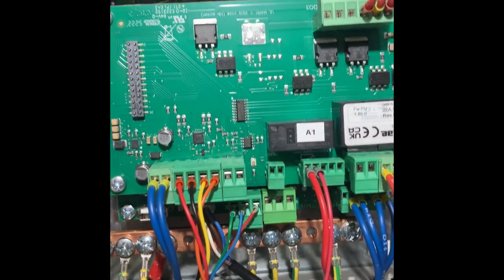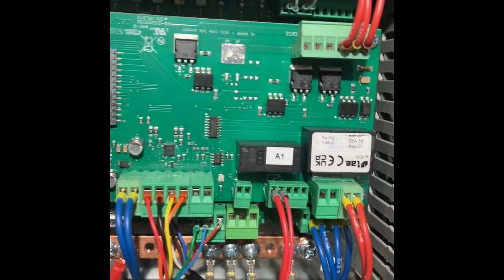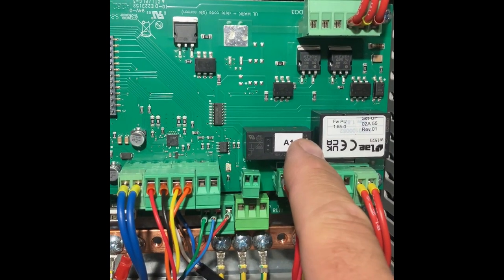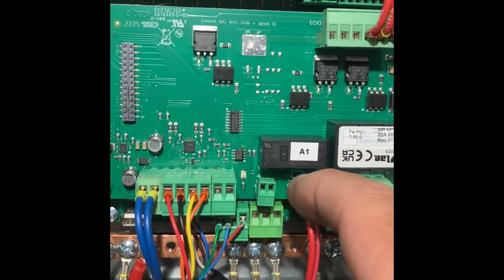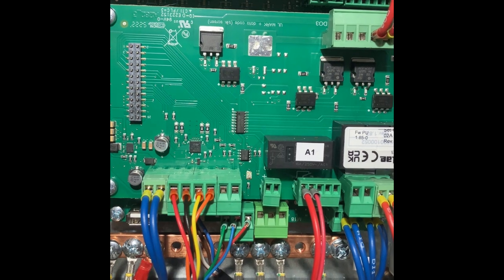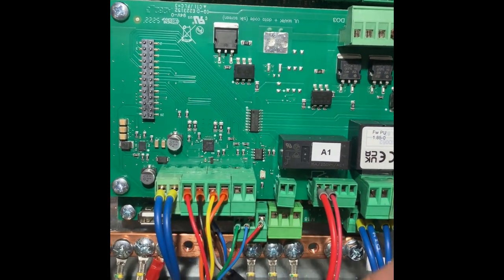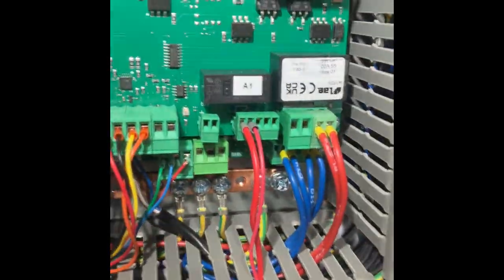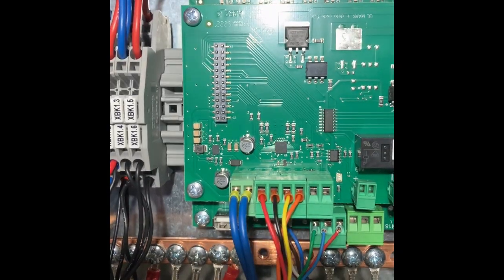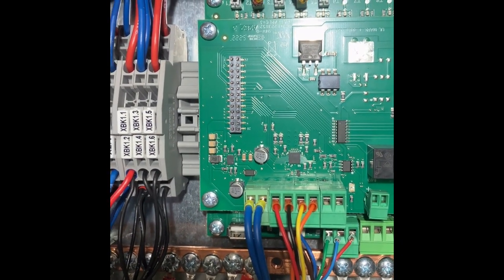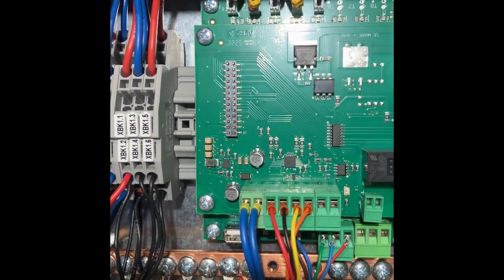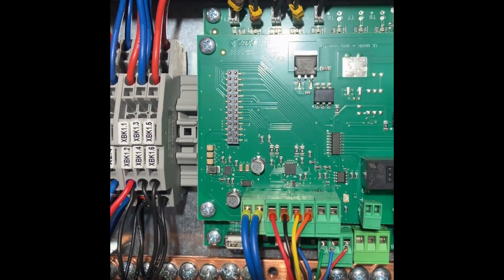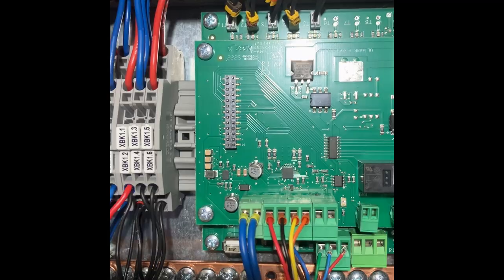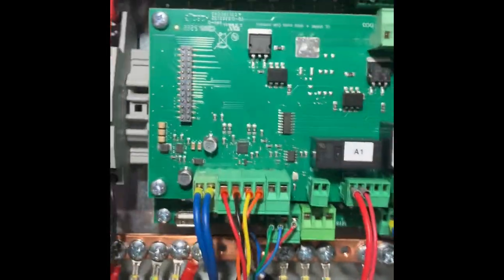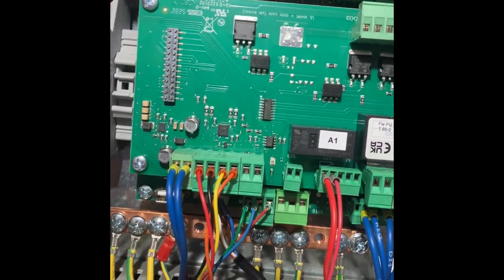All right, compressed air friends. So moving right along here, we are working inside of a Sullair variable speed dryer here, and we come to our control board here, and what we're doing is we are tying in the fault contacts so that if this dryer faults out for any reason, the other end of this wire here is connected to the Aero panel to a digital input there, which you'll see when we go to terminate in the Aero panel, so that if the dryer faults out, the Aero picks it up, registers it as a fault, and then we'll send out an email to the appropriate people saying, hey, dryer number 3 faulted out, you might want to go see what's going on. So tying into the digital inputs of an Aero are a little bit different.